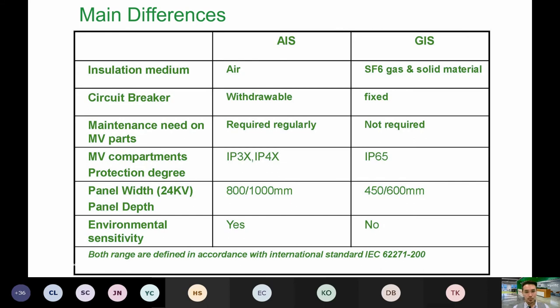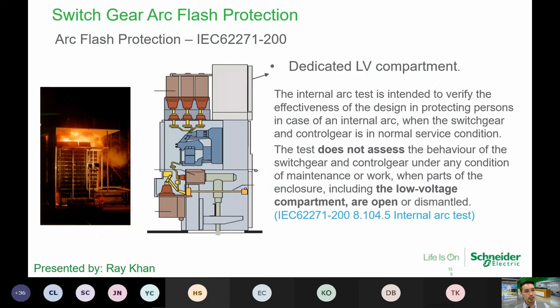Okay, so very quickly I'll move on to one of the key points, which is the standards themselves. So the standards in here talk about the arc flash protections. So this shows the importance of having a dedicated LV compartment. It also shows how the test is actually performed. So in the event we have to do maintenance for the LV components, we don't have to open up the full panel. So you can see in here, this is what they do. For the testing, they put cotton-like materials around the panel. And then there will be an arcing, and that's where the panel actually blows up.